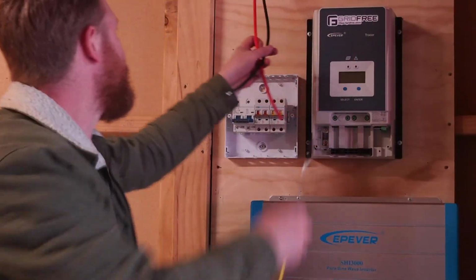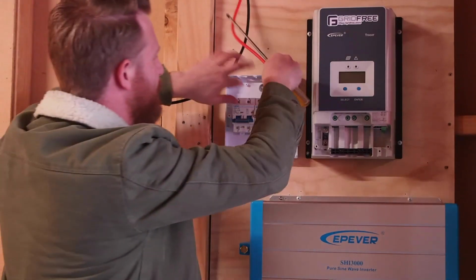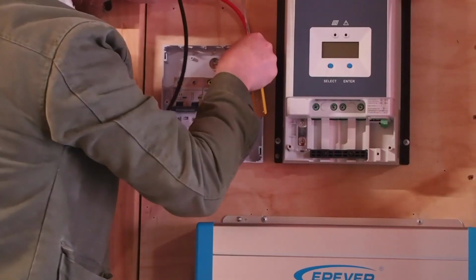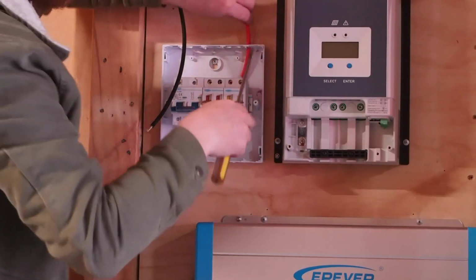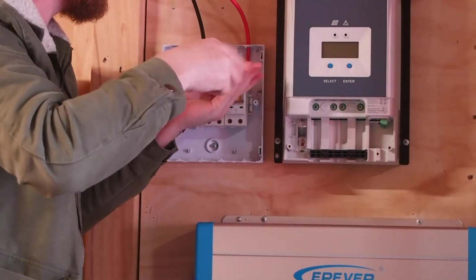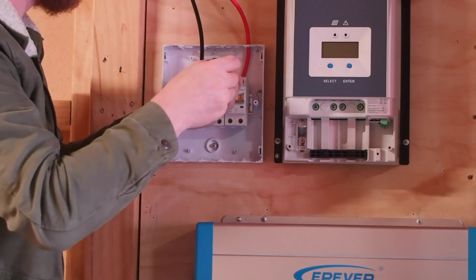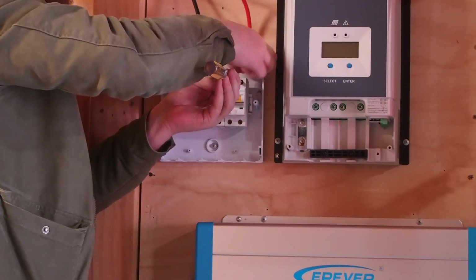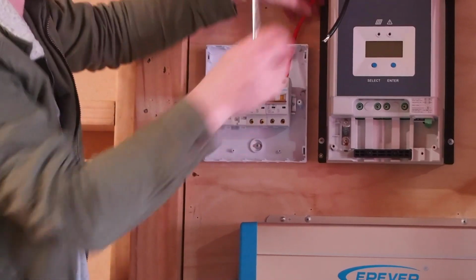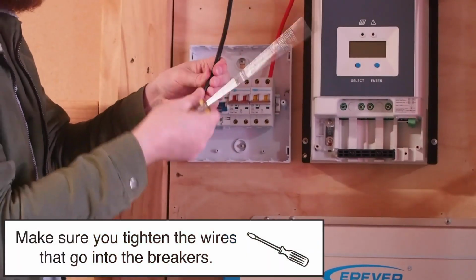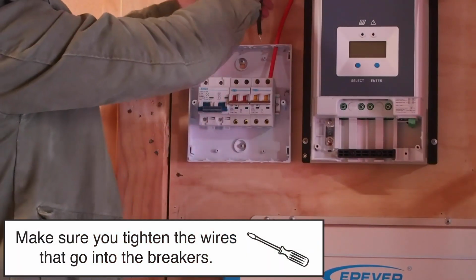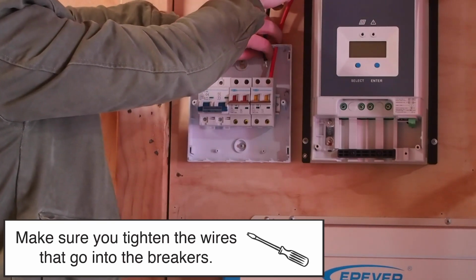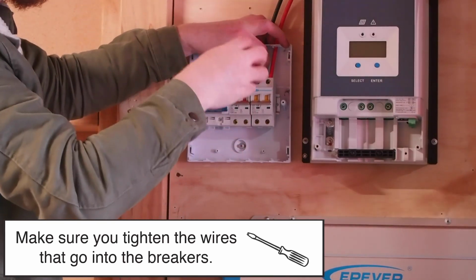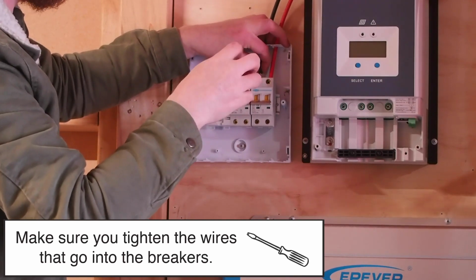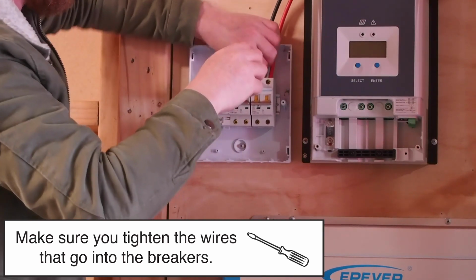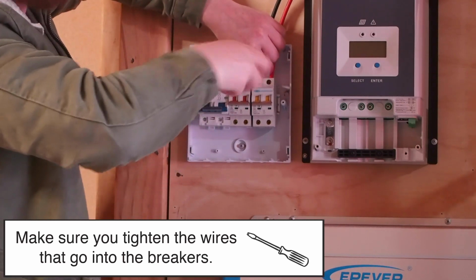And we're going to terminate this into this circuit breaker here. Now when you screw these into the circuit breaker, you want to be making sure that you're definitely getting these in the right place, right between the clamp for the circuit breaker. Now you want to make sure these are nice and tight when you're tightening up the cables in the clamp, because if any of the connections are loose, they can get even more loose over time and cause a high resistance part in the circuit, which will give you a less efficient system and may cause things to get too hot.